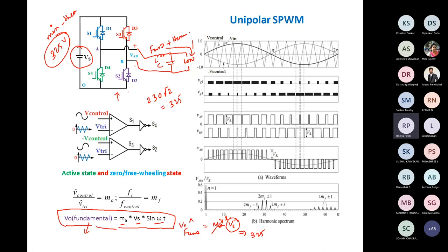But when we derive this equation, we neglect so many things like switch voltage drop and filter drop, etc. So we need to consider some margin for a practical design, and you will see that we need around 380 to 400 minimum DC bus voltage to get 230 at the output.